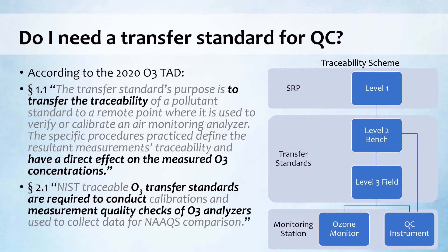So back to the question: do I need a transfer standard for QC? In the 2020 Ozone TAD Section 1.1, the purpose of a transfer standard is to transfer traceability, which will have a direct effect on the measured ozone concentration. Here's a simplified traceability scheme. Your transfer standard is verified against the Standard Reference Photometer, and then that traceability is transferred to the ozone monitor and to the QC instrument. If the QC instrument isn't used to adjust the ozone monitor, then one could assume it's the end of the line, much like an ozone analyzer, and could therefore be treated like an analyzer.